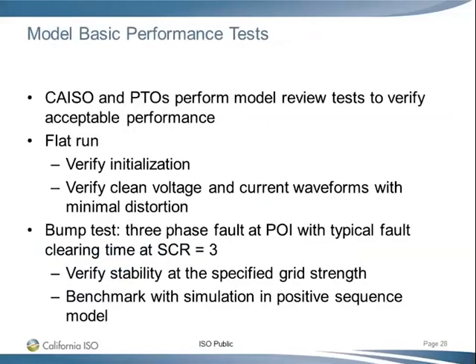Then for the performance, we will run model performance tests similar to what we do with the positive sequence model. So the test with a flat run is to verify initialization, and verify the clean voltage and current waveform. We are going to look at the three-phase waveform and make sure it is a clean waveform with minimum distortion. Then the bump test is a three-phase fault at the POI with a typical fault clearing time.